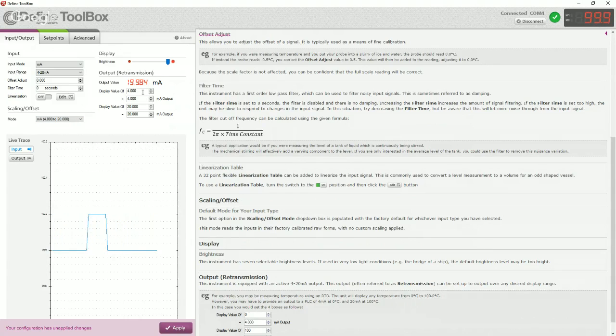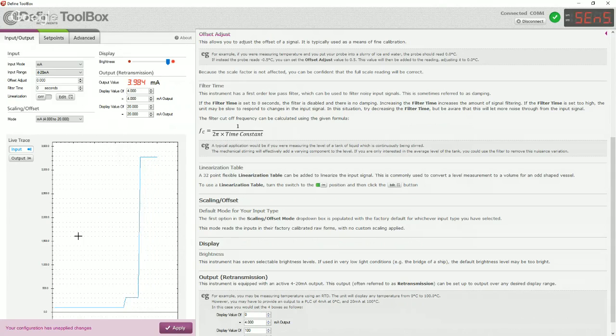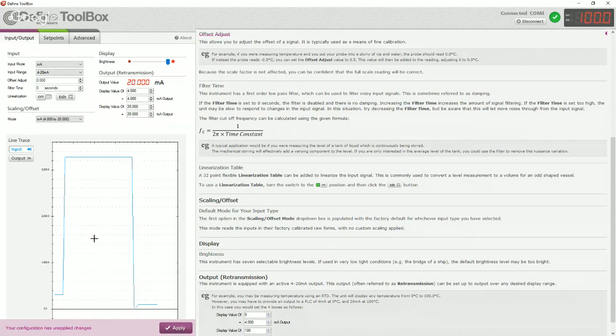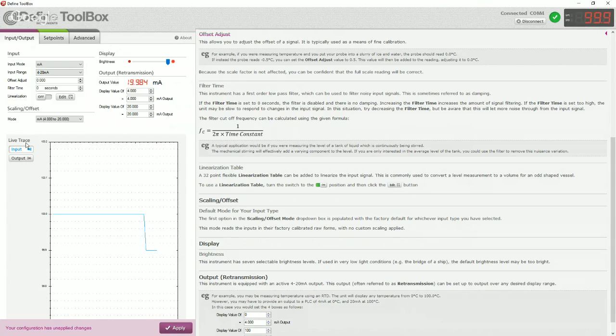And we're going to have retransmission so that a display value of 4 milliamps in is 4 milliamps out, and 20 milliamps in is 20 milliamps out. So that's just a very basic setup. You can also see the live trace down the bottom here, which is actually showing the input signal. So if I unplug the input for a minute, you'll see that the signal jumps up, and then when I plug it back in, it'll jump back down again. So that gives you an up-to-date view of what's happening, which is quite useful. The same thing happens for the output as well, shown here in red. Okay, so that's the input setup.